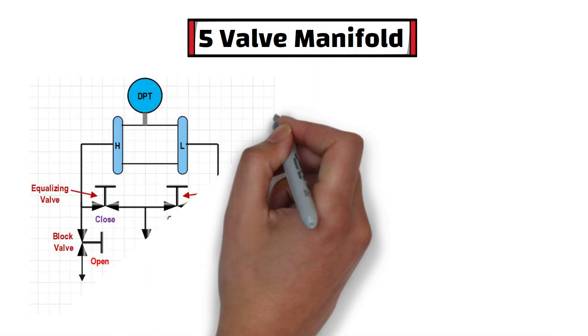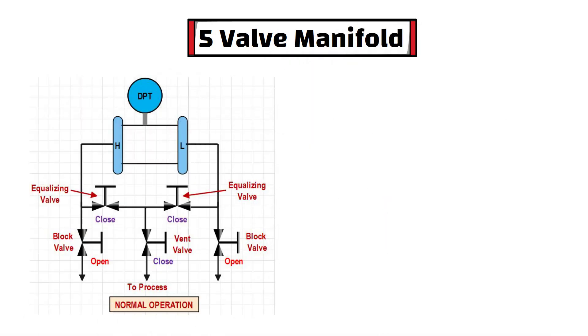Now, let's take an example of five-valve manifold. As you can see in normal operation, both block valve is in open position and both equalizing valve is in closed position. And vent valve also is in closed position.